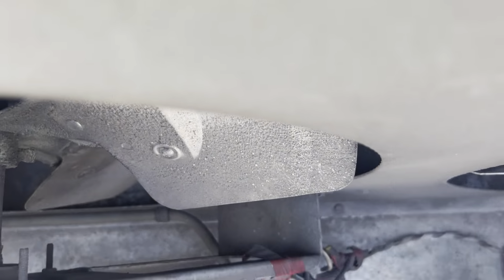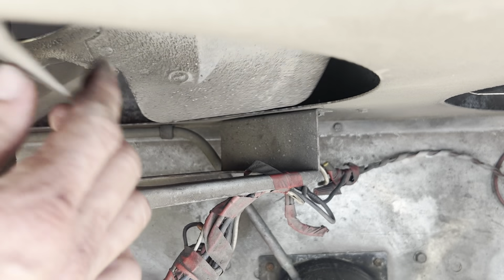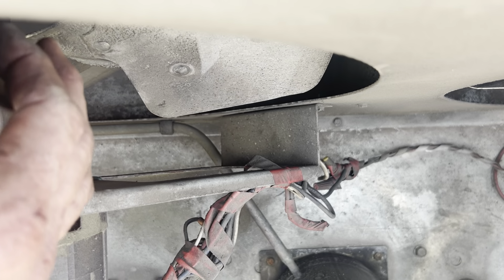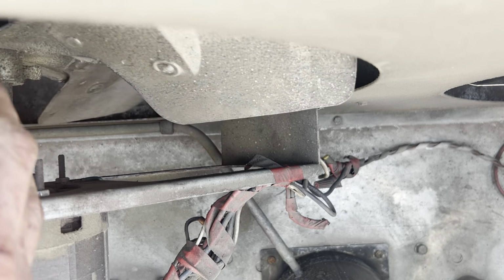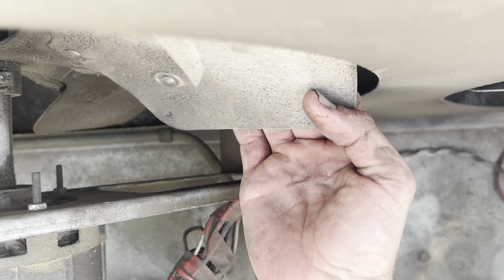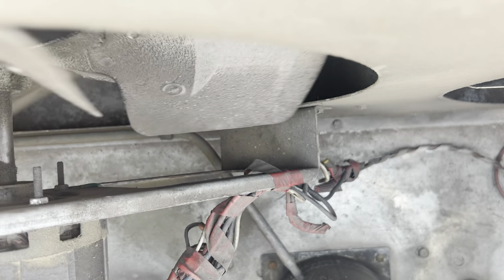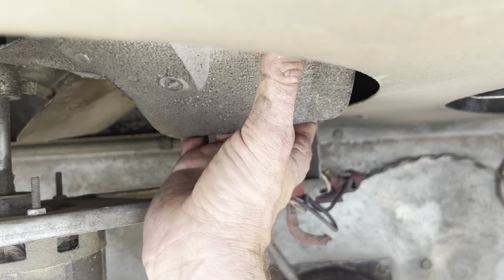I'm gonna change this camera angle. All right. The hood system's running right now, by the way. I'm gonna bypass that switch. I'm gonna direct wire it. Look at that. So that one's angled way in. That one's angled way out. Way in at an angle. There's no way we get this right monkeying with it manually. But to be honest, we're better off running one fan than doing what they're doing right now. That one is way, way gone.